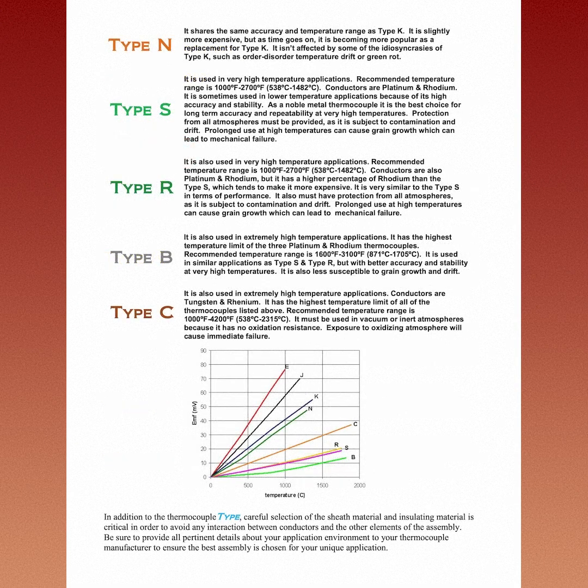Type N shares the same accuracy and temperature range as Type K. It is slightly more expensive, but as time goes on, it is becoming more popular as a replacement for Type K. It isn't affected by some of the idiosyncrasies of Type K, such as order-disorder temperature drift or green rot.